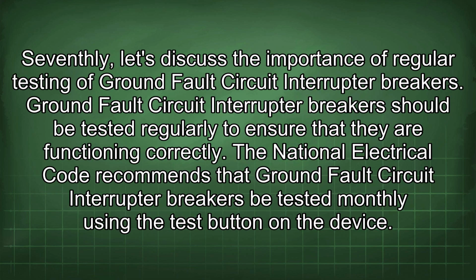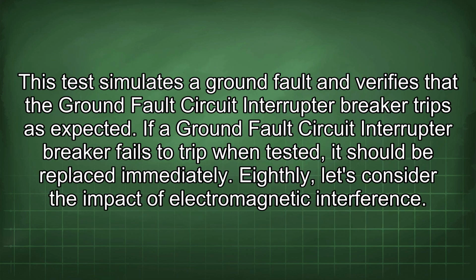Seventhly, let's discuss the importance of regular testing of ground fault circuit interrupter breakers. Ground fault circuit interrupter breakers should be tested regularly to ensure that they are functioning correctly. The National Electrical Code recommends that ground fault circuit interrupter breakers be tested monthly using the test button on the device. This test simulates a ground fault and verifies that the ground fault circuit interrupter breaker trips as expected. If a ground fault circuit interrupter breaker fails to trip when tested, it should be replaced immediately.